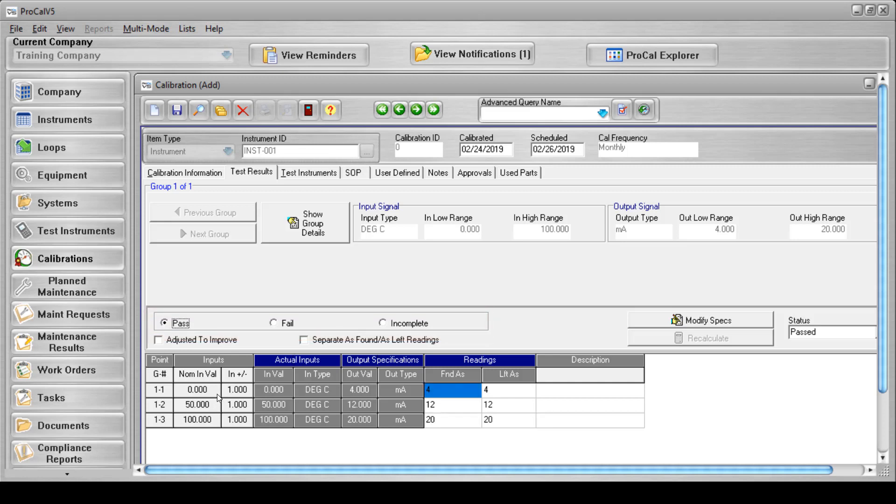If the incomplete radio button is selected, the calibration remains in a state of limbo as far as its results are concerned. A calibration that is saved as incomplete cannot be finalized unless you have configured your company settings to allow that.